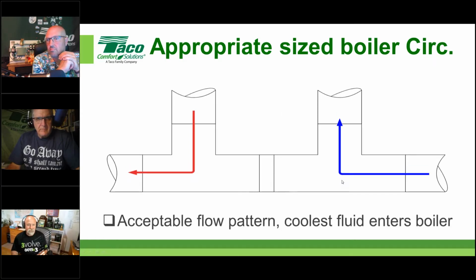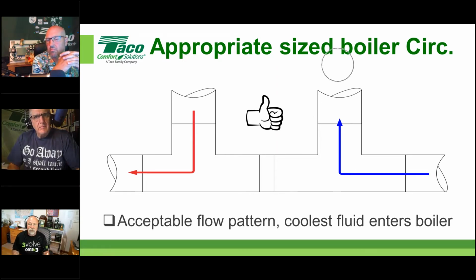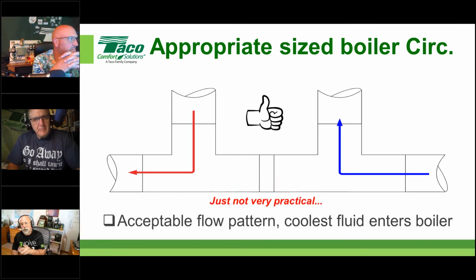Another thing people have said is, hey, what if I could get the flow in the boiler circulator to be the same as the boiler flow in the system? I'll give it a thumbs up, but it's not very practical to do. If you think about it, if I have a circulator here feeding flow back into the heat exchanger, and a circulator out here feeding out to the system, what's the likelihood of those two giving me exactly the same flow and head? It's almost impossible without balancing apparatus and adding a bunch of time and money to the system.